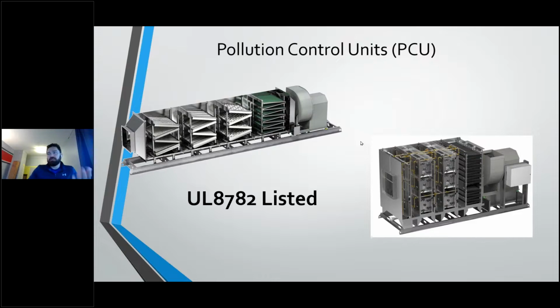A filtered unit is going to be expanding stages of filtration from a 2-inch aluminum mesh all the way up to a top-of-the-line MERV filter, followed by carbon trays. Carbon is what's going to take the smell out. Or an electrostatic precipitator unit, which, depending on manufacturer, is essentially going to come in three sections, where there's either a positively or negatively charged ion in the first section, then the opposite in the second section, so that it attracts to it, and then you're going to have your carbon filters to finish that out, and that removes the smell.